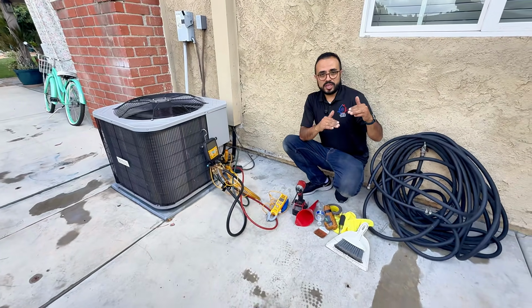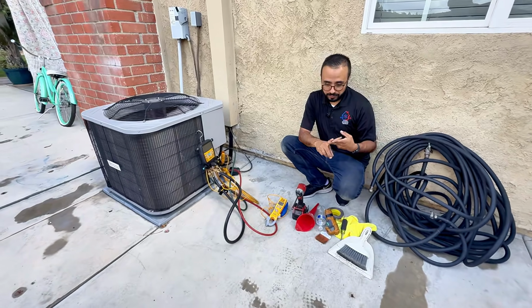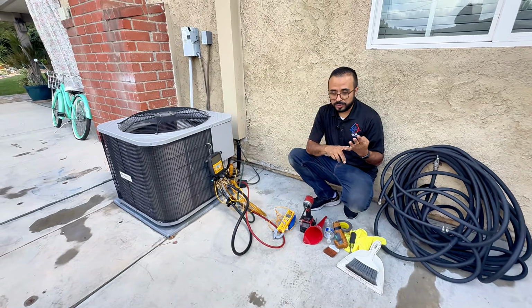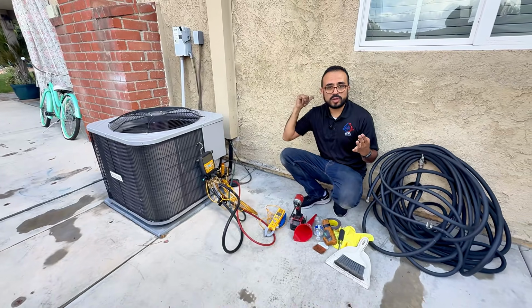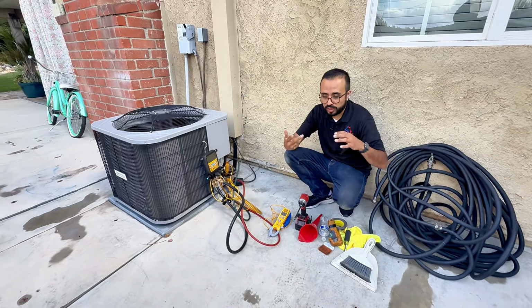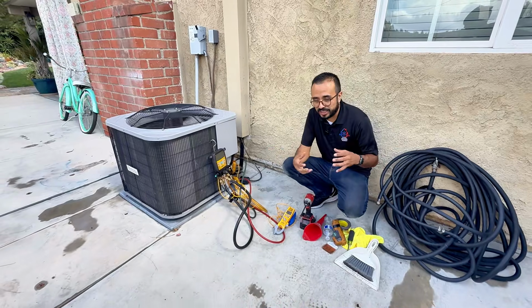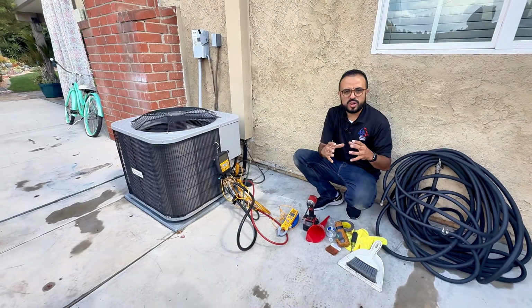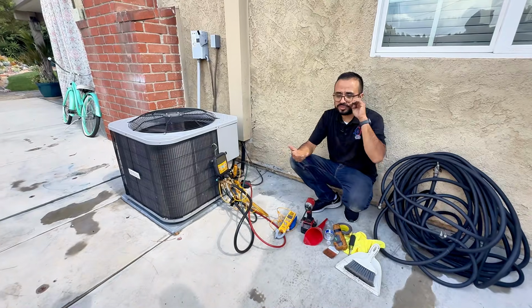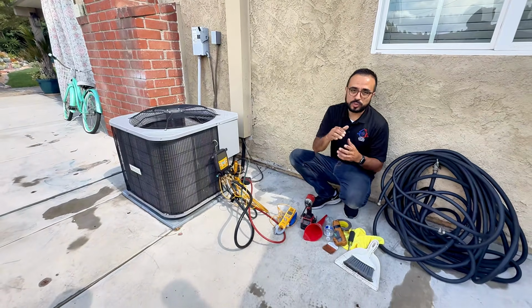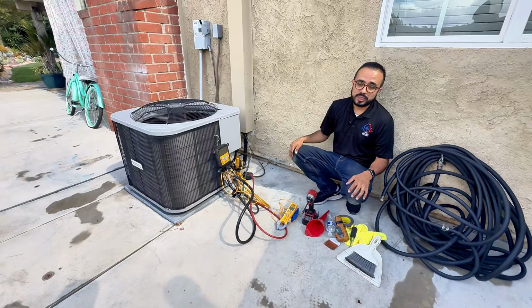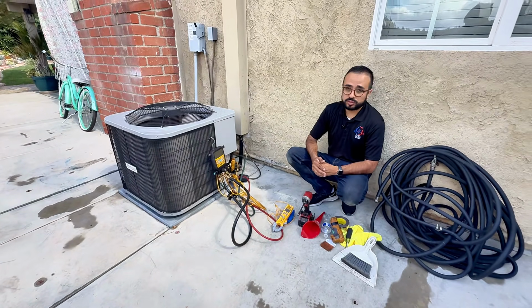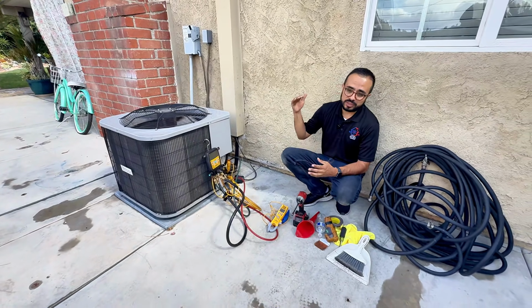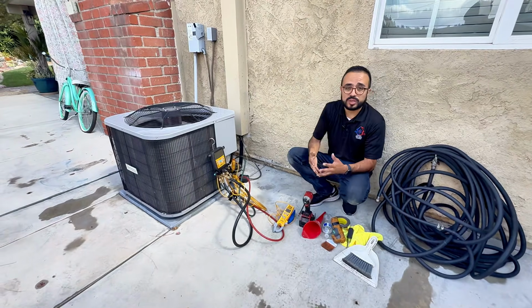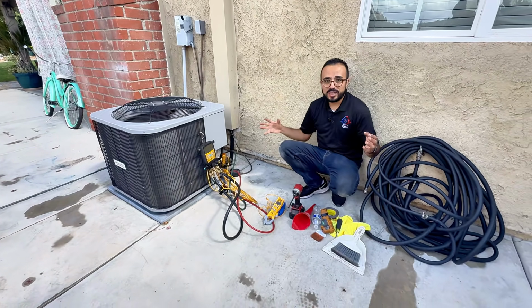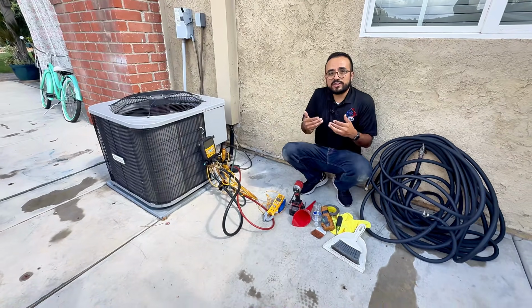Do you remember all the things that we did? We checked the filter, the supply vents were open. We checked the ductwork, the flame sensor, we cleaned it. I did check the squirrel cage, and I did forget to show that. But the squirrel cage, you're seeing if there's any lint, any dust. Sometimes it's so dirty you do have to remove it and clean it outside. But it was in good condition. All the wires were connected. All my capacitors were working well. Everything was well. For my delta T right now in cooling, I'm getting about 21 degrees. I was able to do all that with just tools that are not that expensive.